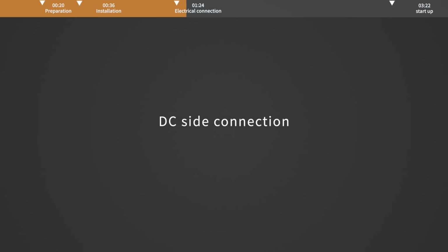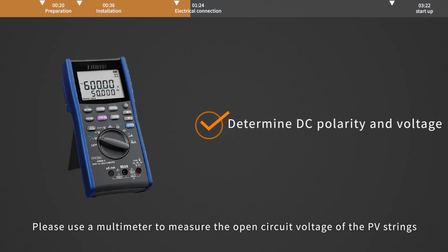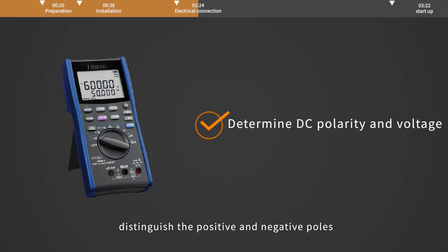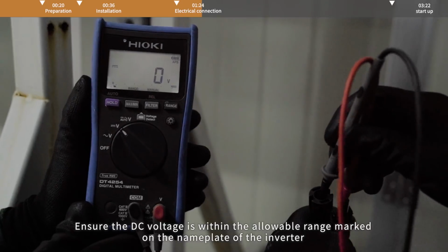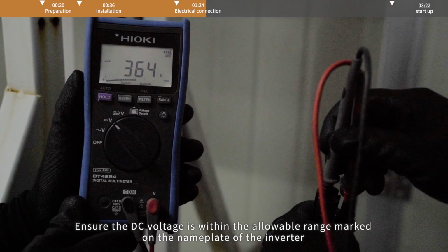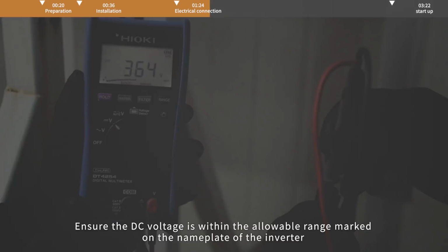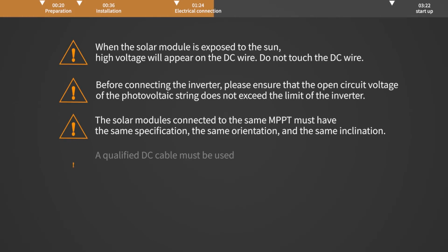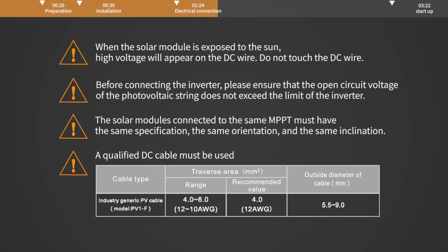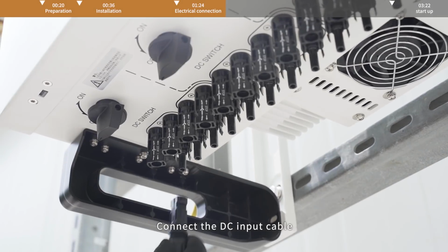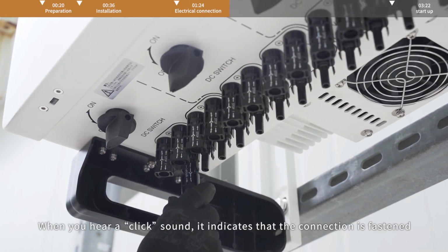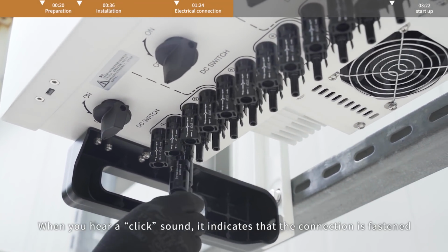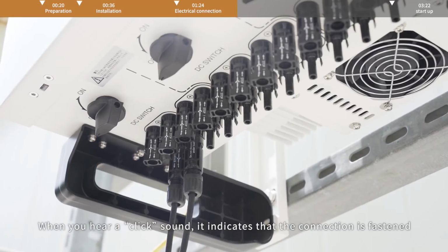DC side connection. Please use a multimeter to measure the open circuit voltage of the PV strings. Distinguish the positive and negative poles. Ensure the DC voltage is within the allowable range marked on the nameplate of the inverter. Connect the DC input cable. When you hear a click sound, it indicates that the connection is fastened.